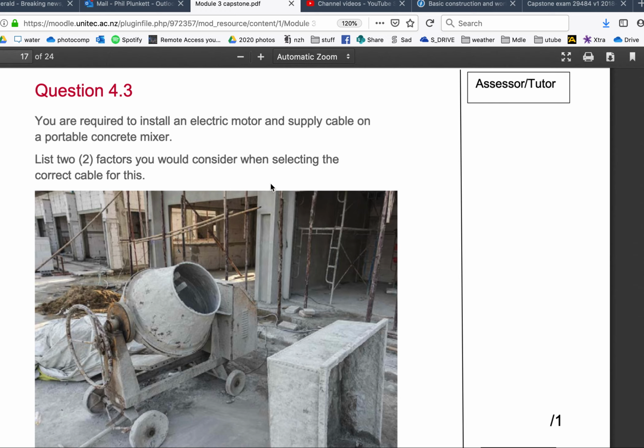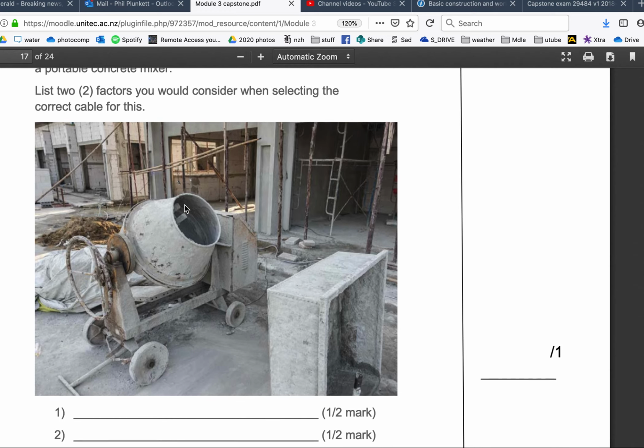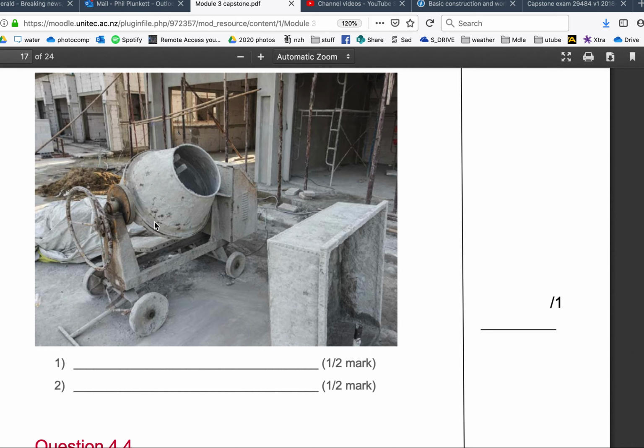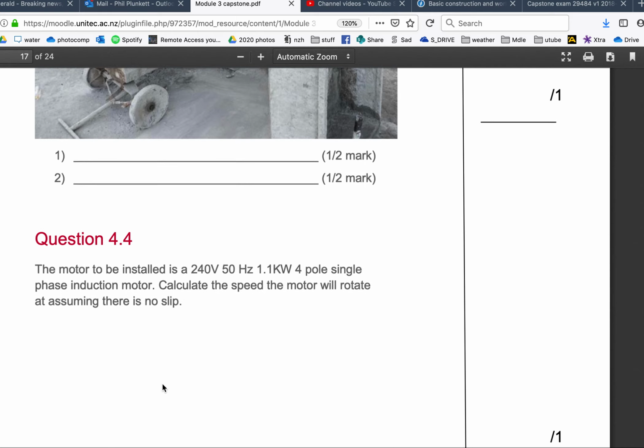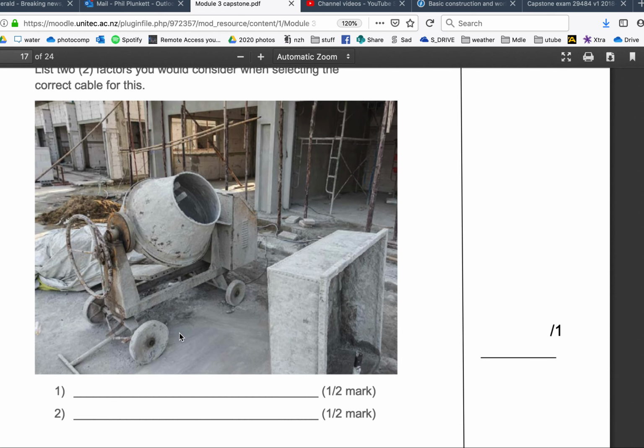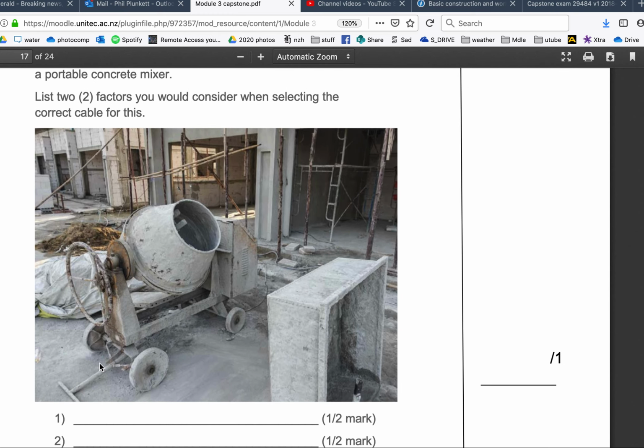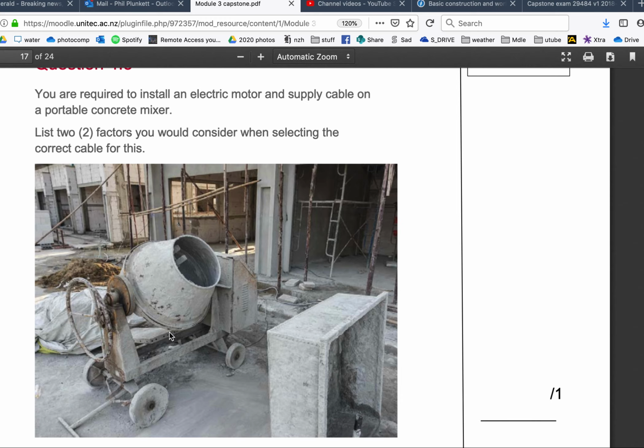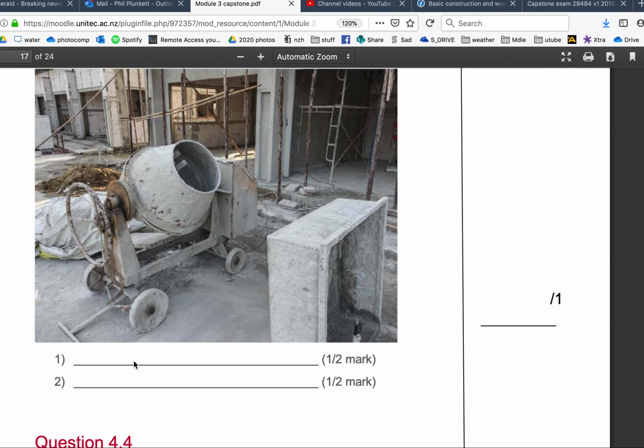And install an electric motor, and there's 2 factors in selecting the correct cable for this. Okay, you're going to have to look at the size of the motor, you're going to have to look at the length of the cable. There'd be 2 things. Environment, so you want a pretty hard kind of insulation material, maybe a rubber plug top, lots of things you can put in there. They wanted you to focus on the cable though, okay? So the type of cable, the length, the size of the motor, because they'll give you your current, they'll give you your volt drop.